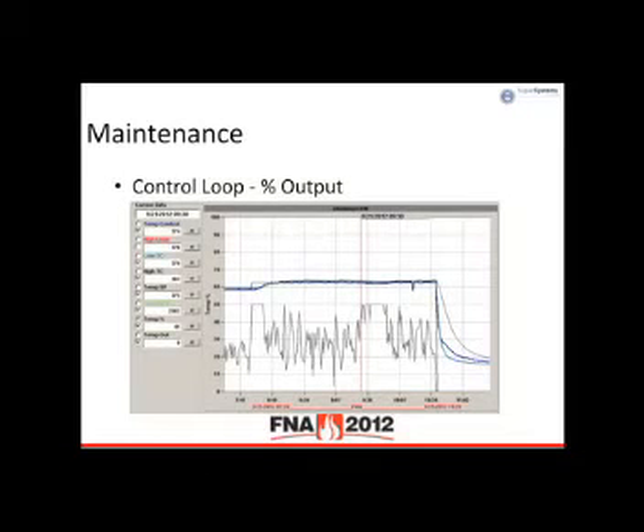So just an example where you can investigate. This is just a recent example. I had a customer call up and say they couldn't get a straight line as far as control. Well, looking at their situation, they had an output limit on their controller. All you had to do is look at the percent output, which is on this chart, and you can see that flat line in the middle. That flat line was limiting the percent output to 50%.